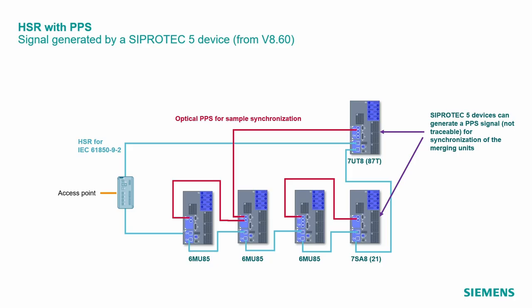With the SIPROTEC 5 devices from version V8.60, this PPS signal can also be generated by the protection device. Keep in mind that this signal is not globally synchronized, but for the process bus it is not relevant to have a globally synchronized signal. What we need for the technology is having all the devices synchronized to the same pulse.